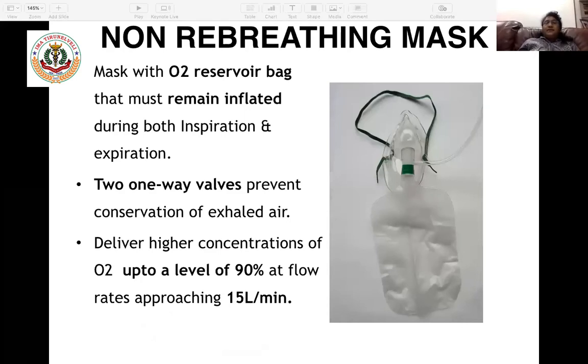Non-rebreathing mask: the mask has an oxygen reservoir bag that must remain inflated both during inspiration and during expiration. Two one-way valves are present in this device. It delivers a high concentration of oxygen, up to a level of 90%, at a flow rate of approximately 15 liters per minute.